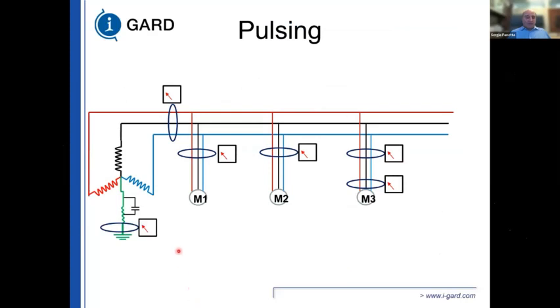So imagine you have this system, you have a resistor connecting the neutral to ground. You get a ground fault on a phase downstream. You turn on the pulsing. Pulsing is basically changing the value of the resistor. Let's say you have a 55 ohm resistor, you change the value of the resistance to 27 ohms. So now the value of the resistor changes cyclically, depending on the state of this contactor, from 55 ohms to 27 ohms, producing a signature that you can actually use to help locate where the fault is.